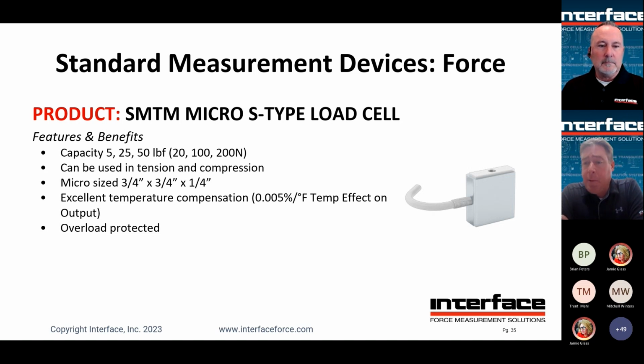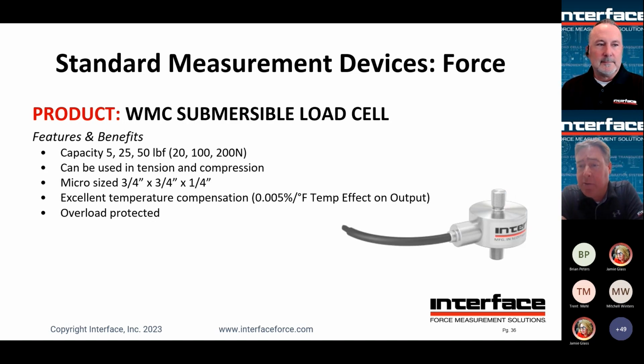temperature performance. Another common factor when you're looking at lower capacity load cells is how do you keep them from being overloaded? If, for example, it's a 5-pound SM load cell, it has a safe overload rating of 150%, so you're looking at 7.5 pounds. It's not a whole heck of a lot and it's relatively easy to damage the load cell. So selecting a load cell that has an overload protection scheme in it is important. This particular load cell is rated for up to 10x of its rated capacity and has actual overload stops EDM machined into the flexure, so it's going to shunt the load around the gauged area past a certain force level.